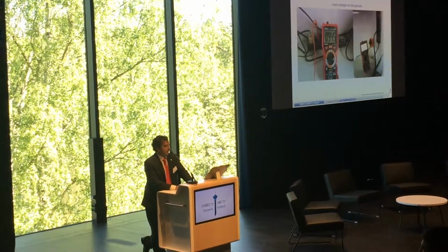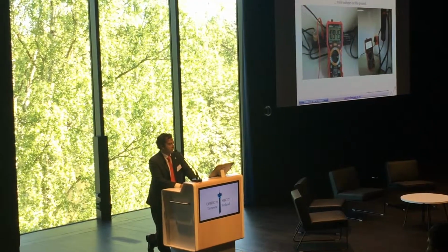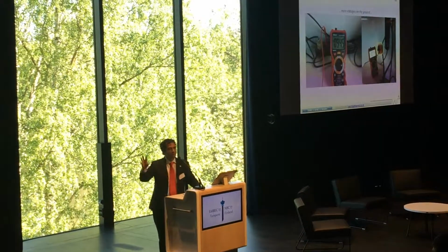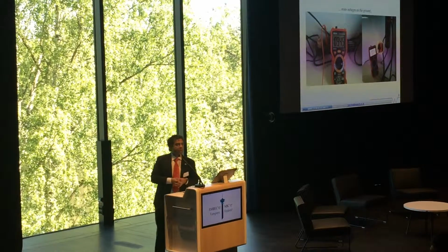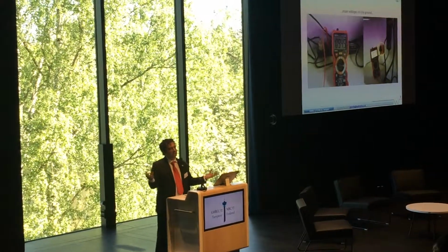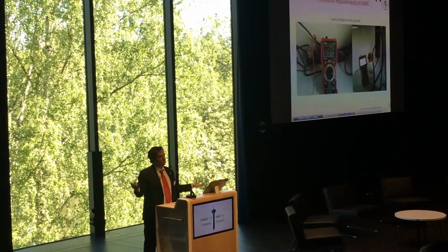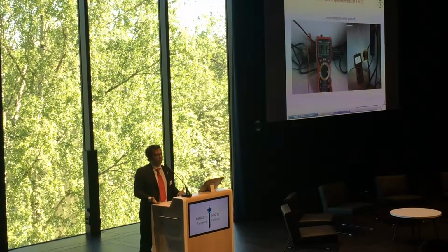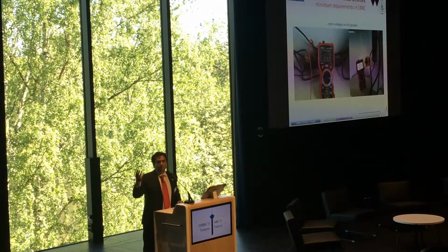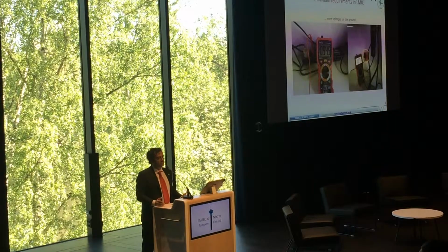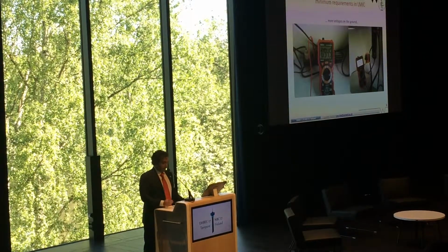Why is that? For several reasons. This was a lab, this was an adapter, and when I took it off, it had no ground. So what's the point of having an equipotential node if then someone puts in an adapter which has no ground?